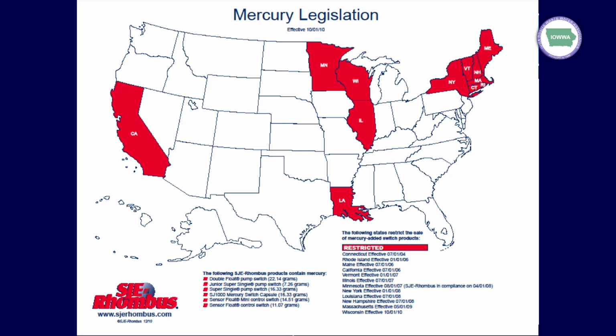When the mercury gets outlawed, was it a mechanical switch or is there something else? No, we have other options besides a mechanical or a mercury switch, so far as turning pumps on and off. I will say from a cost standpoint, mercury and mechanical float switches, the reason they're as popular as they are is because they're very, very low cost, effective way of actuating, turning a pump on and off. So my guess is, for the states that are in red up there, we sell a ton of mechanical switches and no more mercury. I would say that if you're in a state that bans mercury, everybody just gravitates towards the mechanical switch.